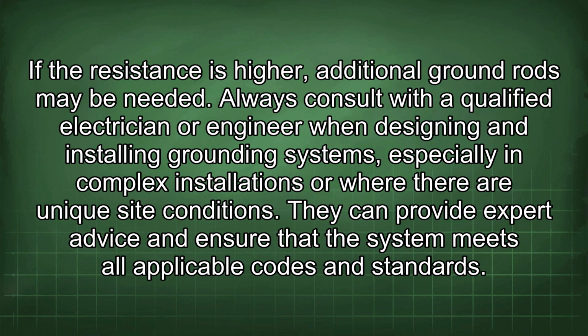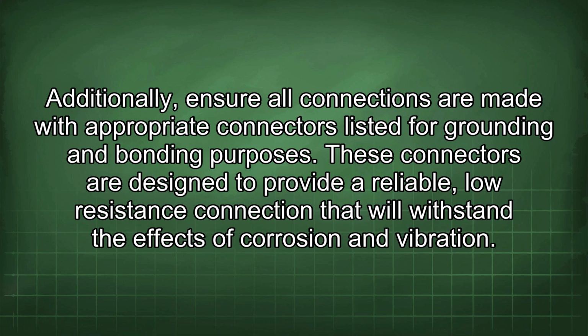Always consult with a qualified electrician or engineer when designing and installing grounding systems, especially in complex installations or where there are unique site conditions. They can provide expert advice and ensure that the system meets all applicable codes and standards. Additionally, ensure all connections are made with appropriate connectors listed for grounding and bonding purposes. These connectors are designed to provide a reliable, low-resistance connection that will withstand the effects of corrosion and vibration.